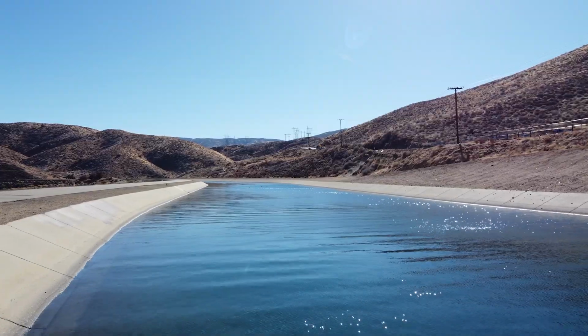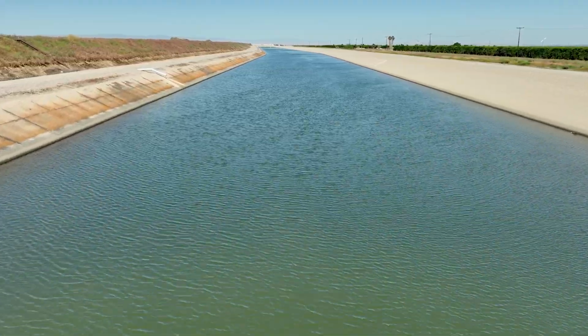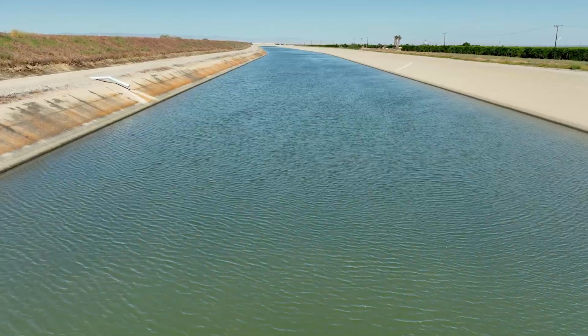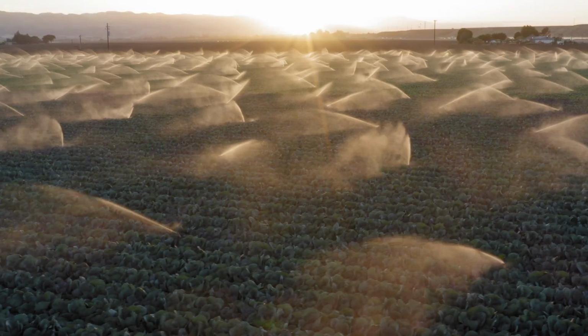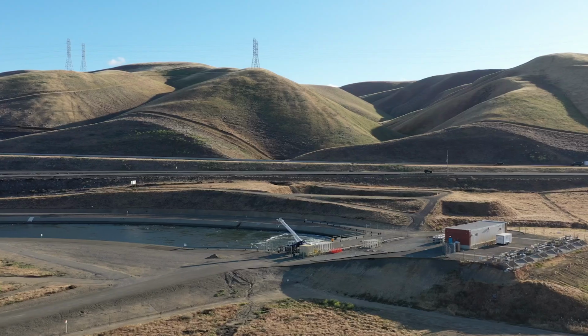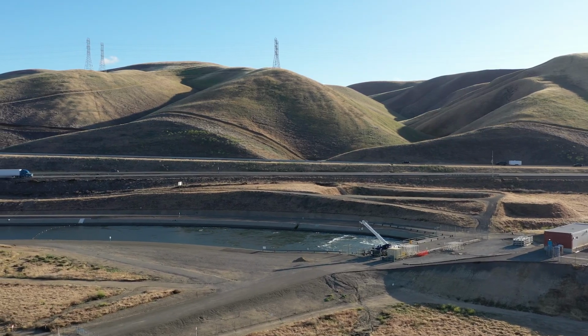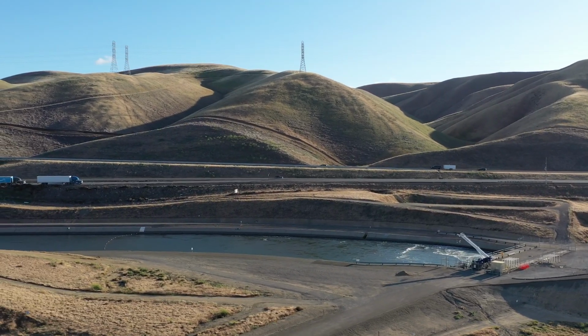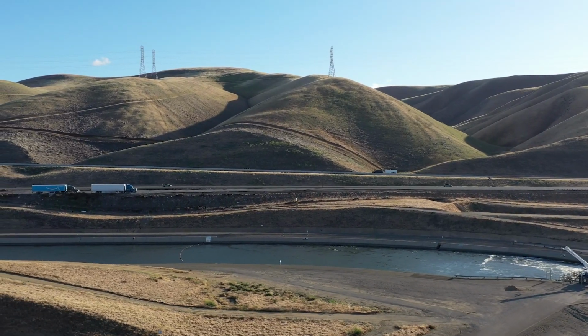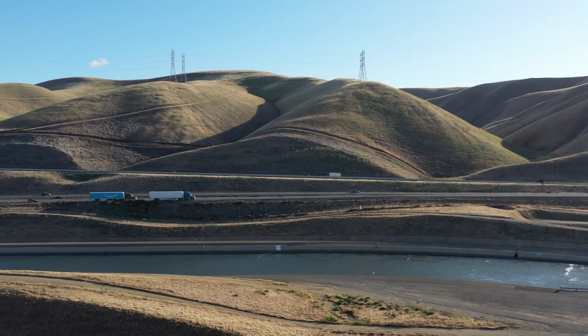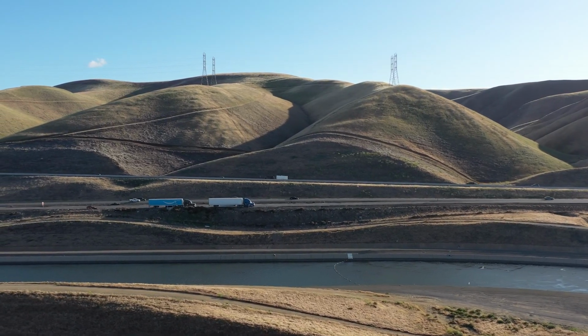The existing system didn't provide real-time feedback, which made decision-making much slower, especially during peak irrigation season. Operators often found out about pump failures only after a reservoir had dropped, requiring urgent manual intervention. Communication failures also meant pumps didn't start in sequence, impacting water delivery.